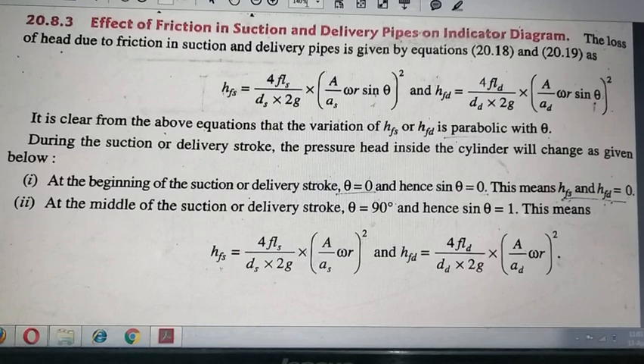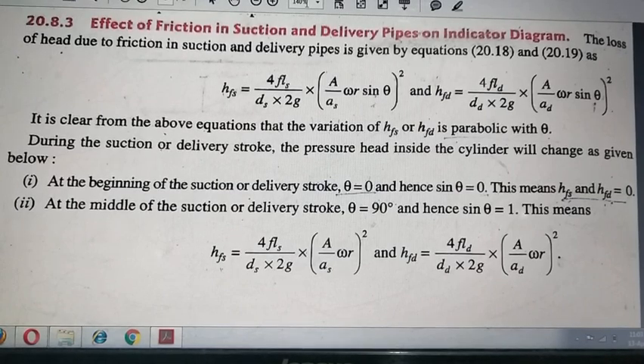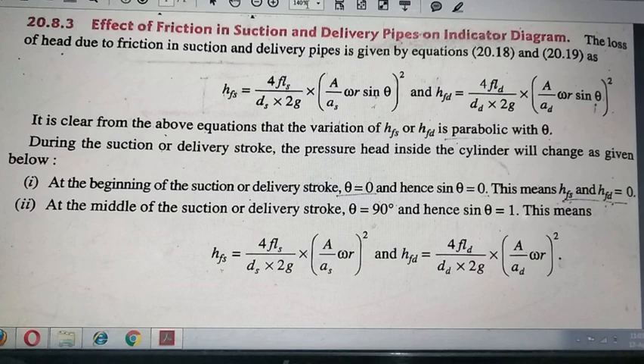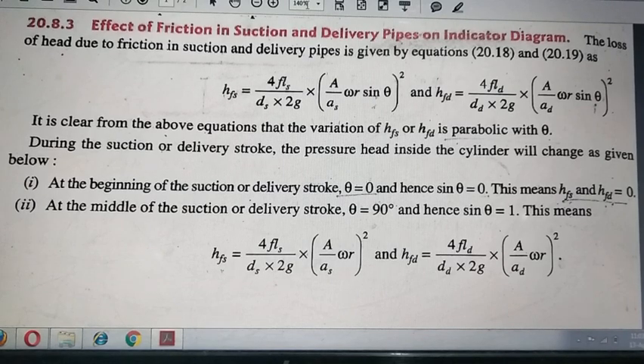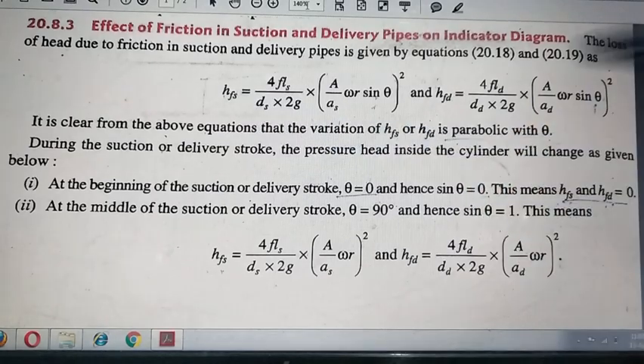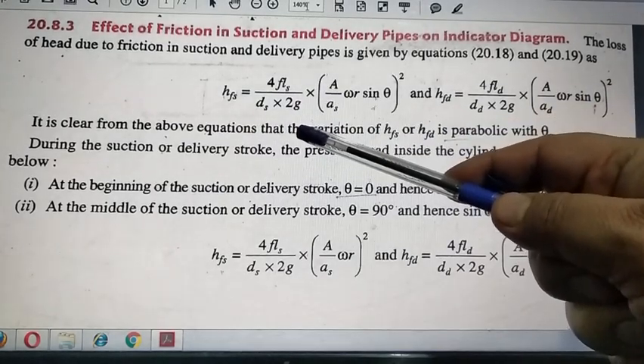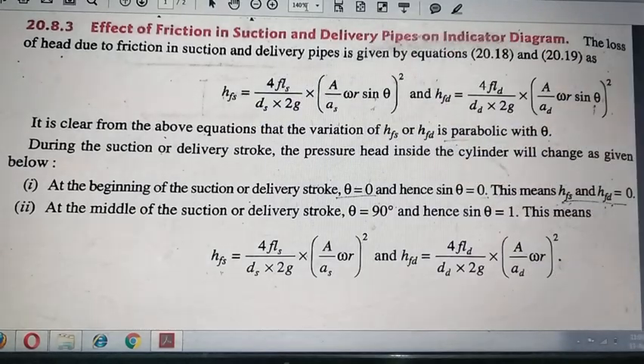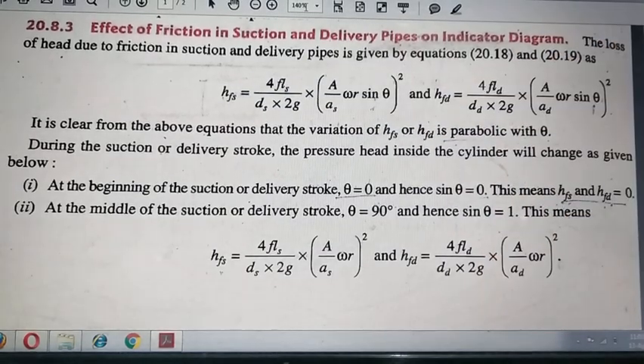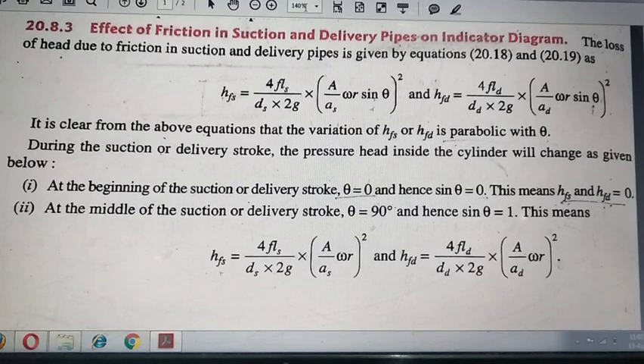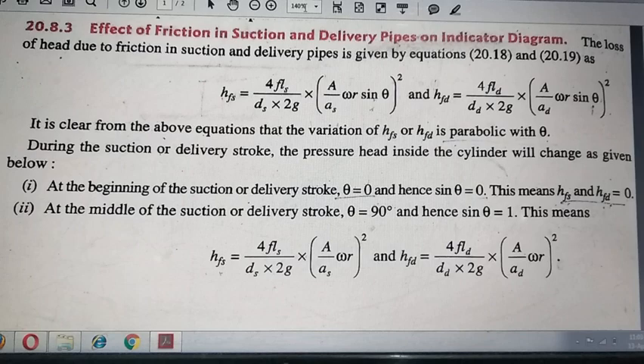If I write this equation for the suction pipe, which we have derived earlier, that is Hfs = 4fLsVs² / ds, where 'Hfs' denotes the friction head for the suction pipe, 'Ls' is the length of the suction pipe, and 'ds' is the diameter of the suction pipe, multiplied by 2g.